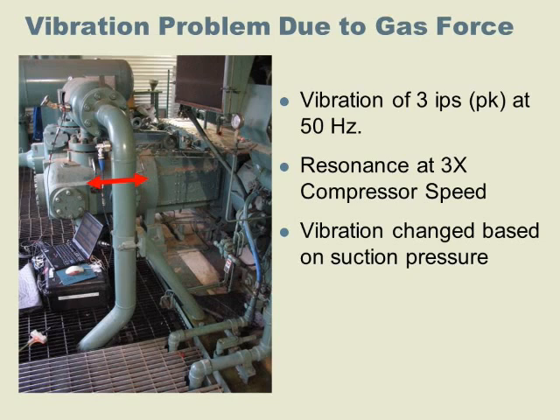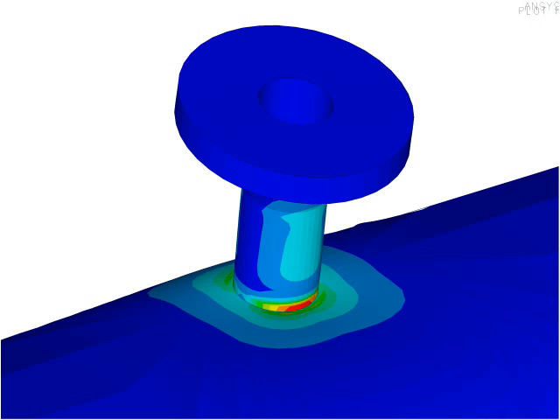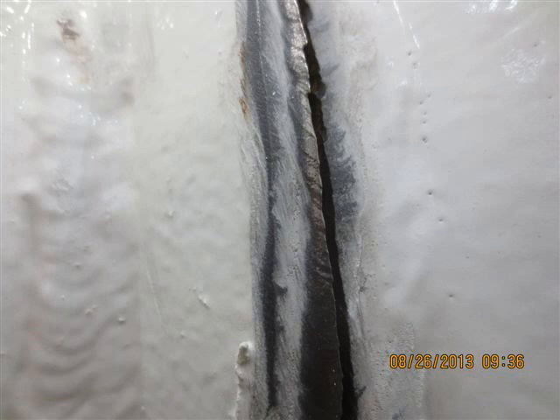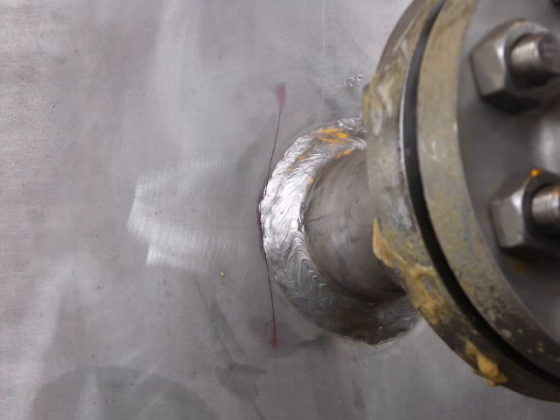Any piping connected to the compressor can be affected and experience fatigue failure. Areas of particular risk include nozzles, small bore piping such as sight glasses and drains, and other small connections.